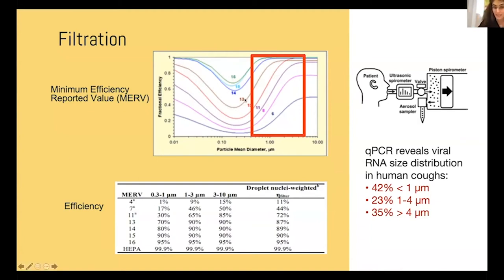And you can follow with me here, MERV-13, orange, and you can follow the efficiency. Above 1 micron, the efficiency is above 85%. So this is where the good news lies. So imagine this, most of the air in your building is recirculated air, at least 80% of it. This 80% is going through a very, very efficient filter. If you hear this and you have some outside air and you're operating and maintaining your building, you don't need to do much more. And you don't need to say, oh, I can't open my building safely, or I need to buy these magic technologies that are not basically vetted correctly.